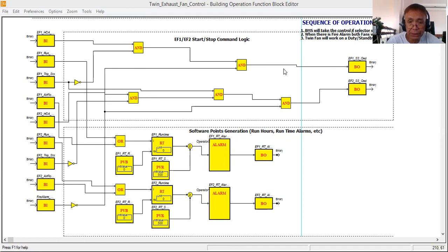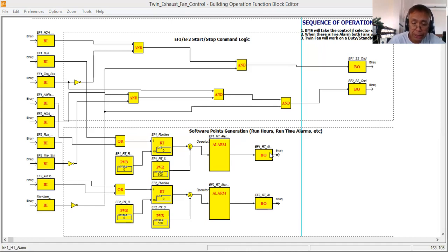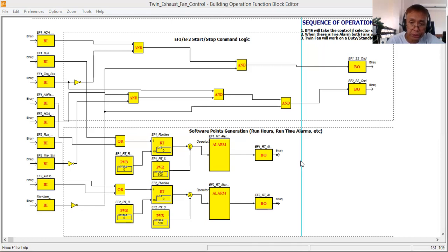I don't think I need to explain the start/stop command again since I already simulated it in my last tutorial. Now, responding to my subscriber's request, I am doing the software point generation. This will generate run hours, runtime alarms, and other software points involved in the twin exhaust fan control. I'll focus on run hours — runtime accumulation — to show you how to do it.